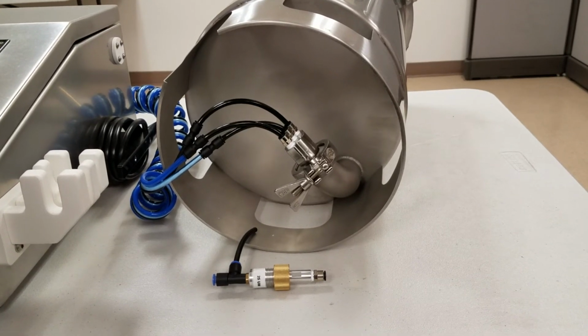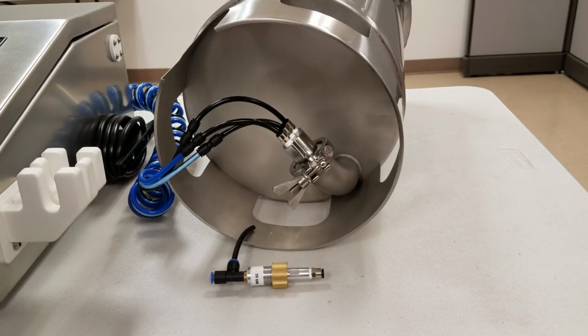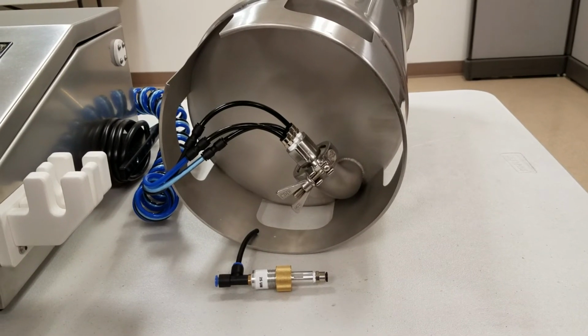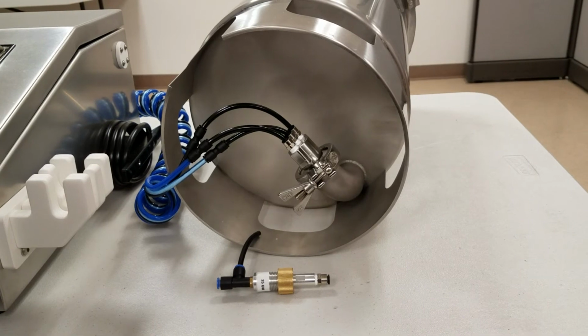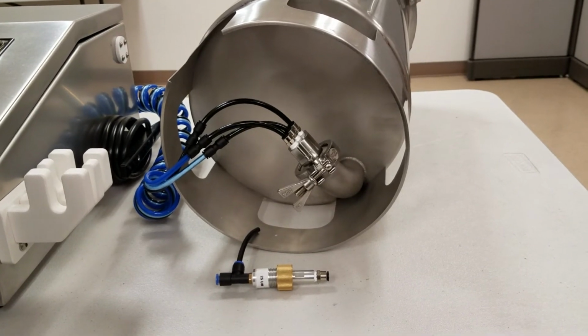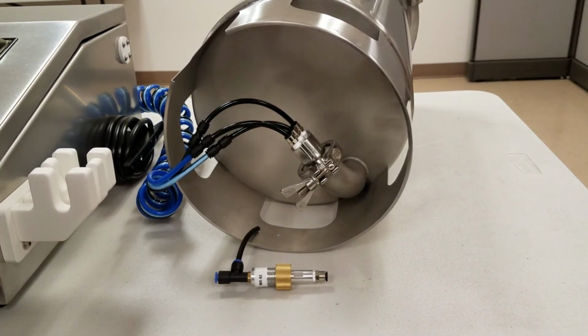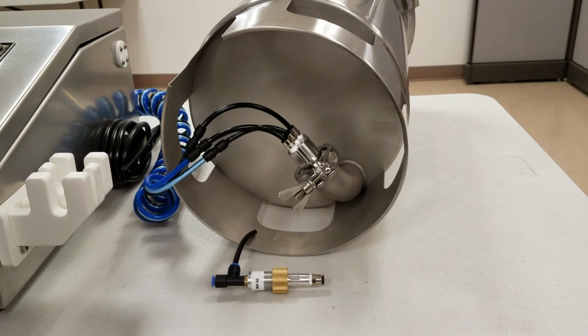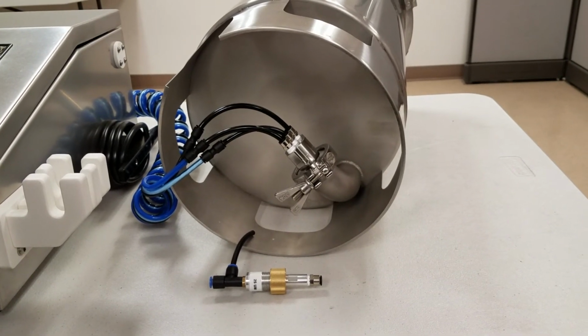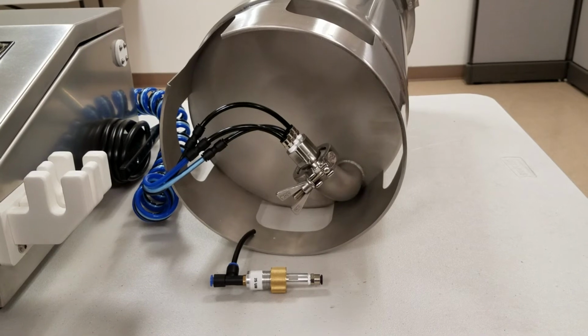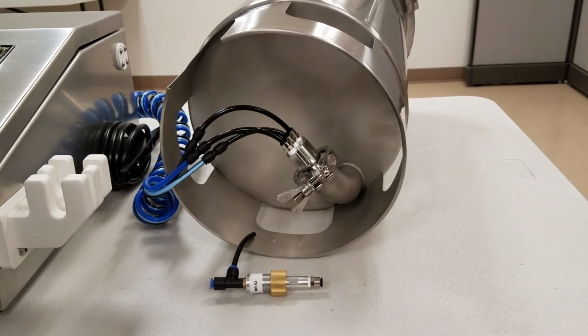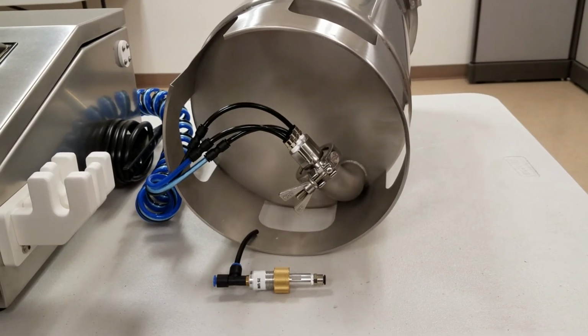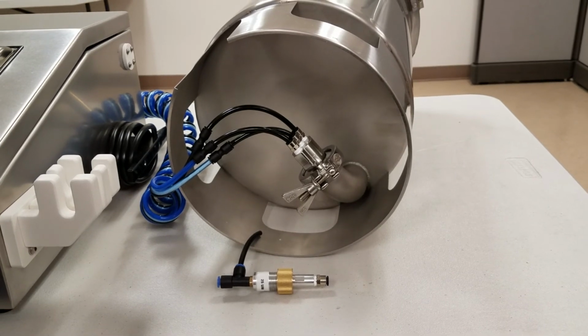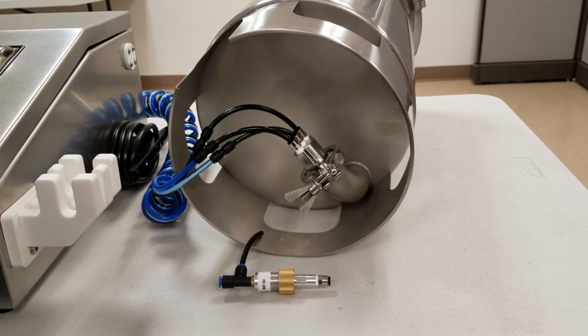the intention is to always run a number of tests without the Orifice adapter connected, as you see in the setup that you see right now, and also to run a number of cycles with the connected adapter so that you can evaluate the pressure decay when a 25 micron hole is present in the canister. So this shows how to include the Orifice adapter on the assembly.